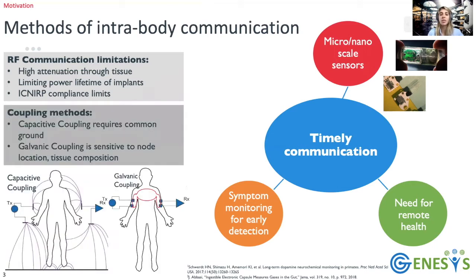Alternative coupling methods have been used for intra-body communication, such as capacitive and galvanic coupling. Capacitive coupling works by transmitting information through coupled electrodes to human tissue with a return path via common ground. Galvanic coupling uses the coupling between two transmitting and two receiving electrodes to transmit information. Both have limitations, which make them unsuitable for an implantable network, such as the one that we're envisioning. In the capacitive coupling case, the common ground requirement makes it unsuitable for an implanted network. In the galvanic coupling case, it is sensitive to node location and tissue composition.